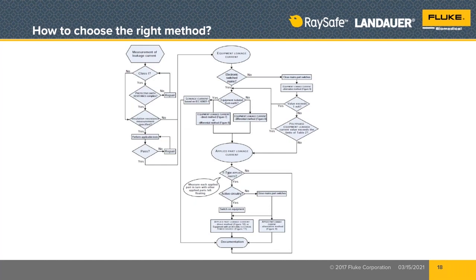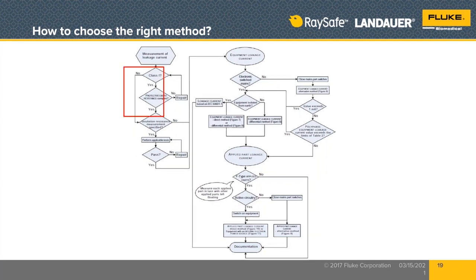In the IEC 62353, and I'm really sorry that this is very, very small, it doesn't work very well fitting on the slide. This is indeed in the IEC 62353 standard itself. There is this decision tree about how we choose the testing method that we will be using. So the first decision point here is: is it a class 1 device or some other classification? And if the answer is yes, then we follow down where it says yes. And the second question is about protective earth testing, I believe.